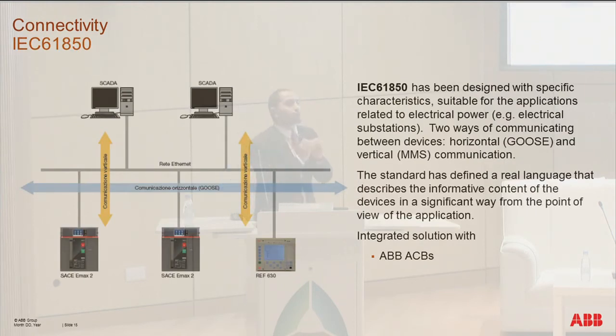The last one, which is the most important protocol now, and in which we are unique, is IEC 61850. We can support IEC 61850, the communication mainly used in MV substations, between LV and MV devices. Now we are complying. It's also an Ethernet protocol, with communication between the LV and MV devices in a horizontal way through GOOSE messages, in order to remotely control the circuit breakers for selectivity communication, and also in a vertical communication with each other through the master, which is the SCADA system. So now we have a summary of the communication protocols for the ABB EMAX2 air circuit breakers: we can provide around 7 protocols. Frankly speaking, it's a lot of protocols that we can provide in the market.